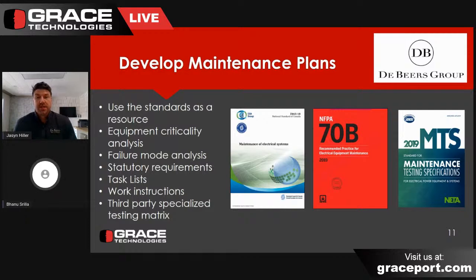We eliminated downtime by simply cleaning the electrical equipment periodically. It assured us that the electrical protective devices would operate per the engineered time parameters, and that posted arc flash labels would allow the worker to dress to the appropriate level of protection for the hazard -- assuring continued service of the electrical equipment.